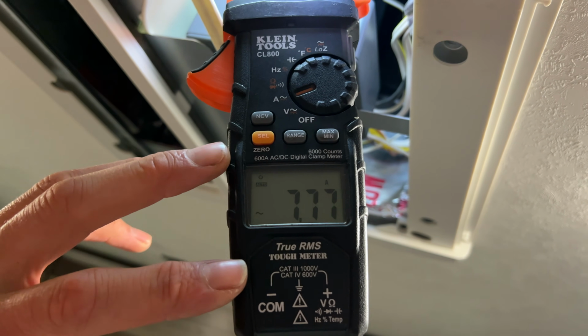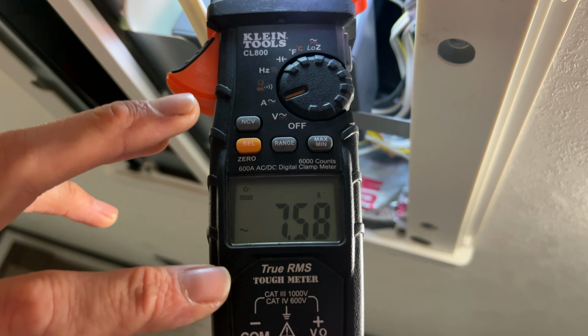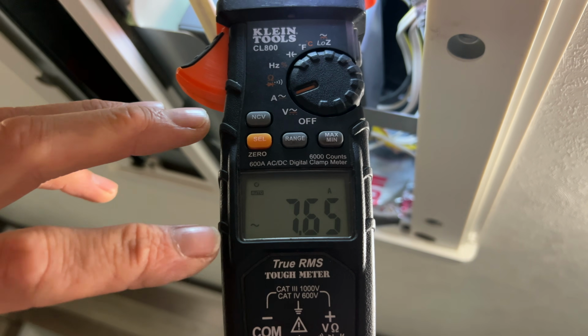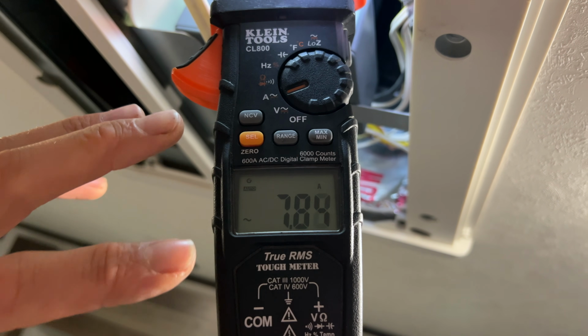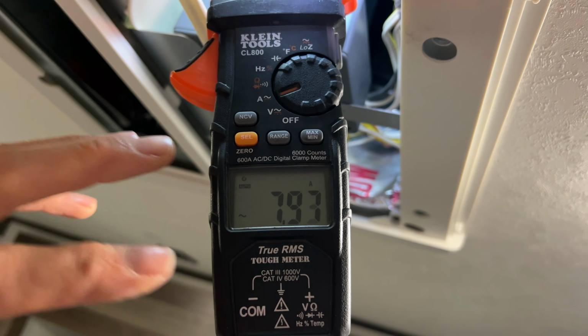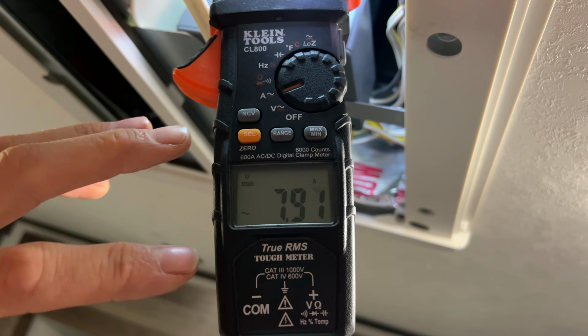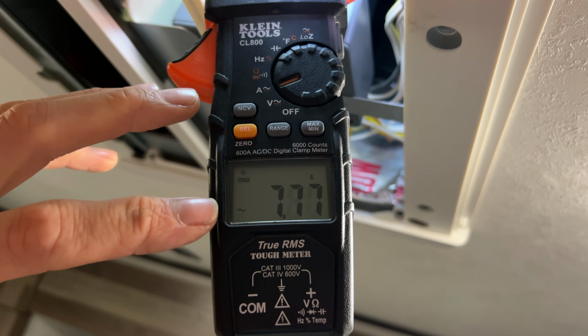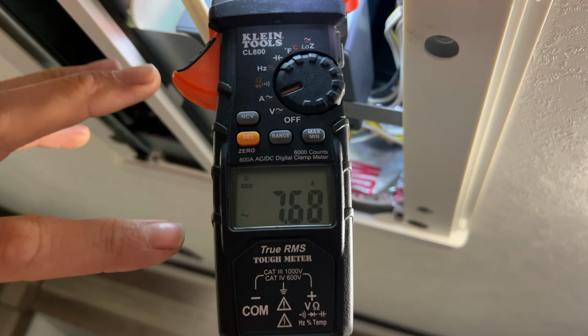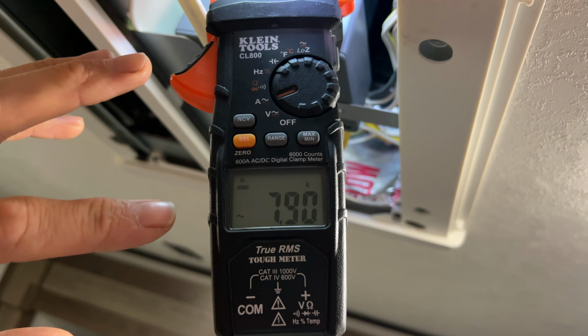Now as you can see, we're reading not quite 8 amps right now. It'll take around 10 to 15 minutes before the AC gets up to full amperage for your proper reading. As you can see, the amps are climbing right now, and you'll verify that based on your outside ambient temperature.